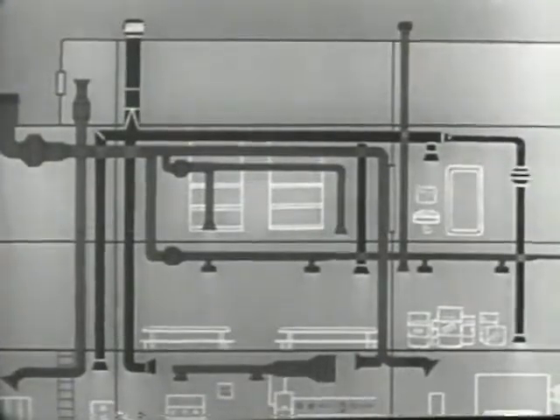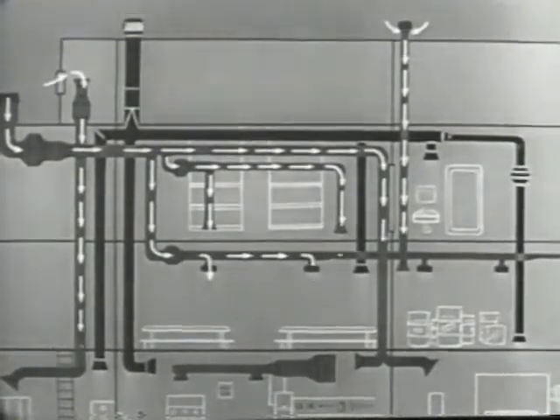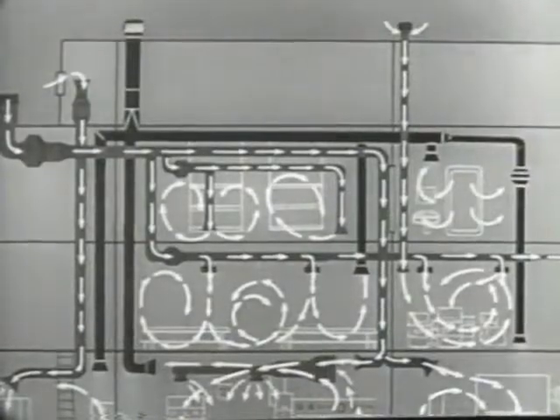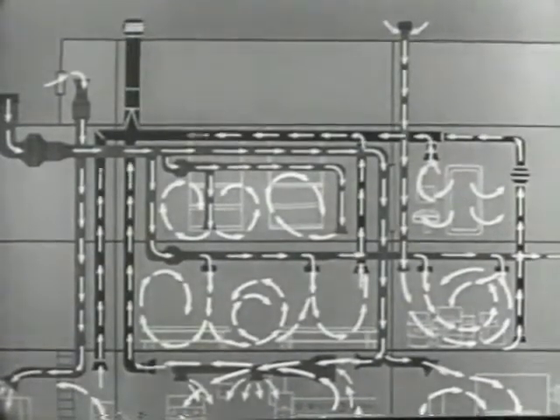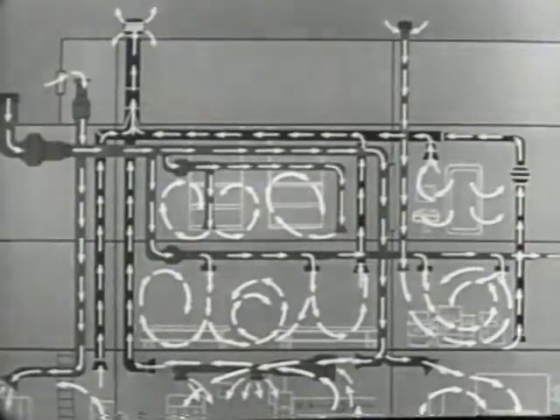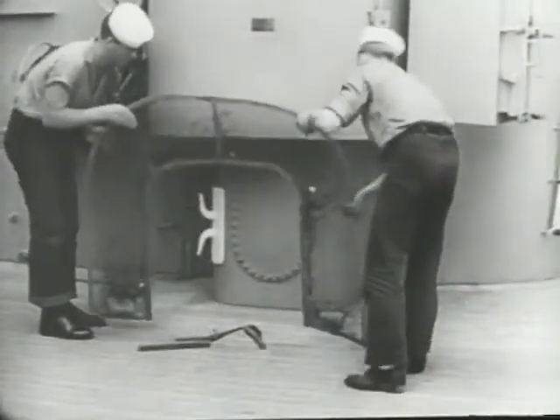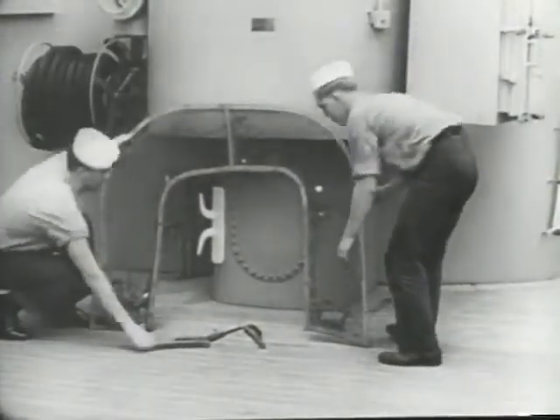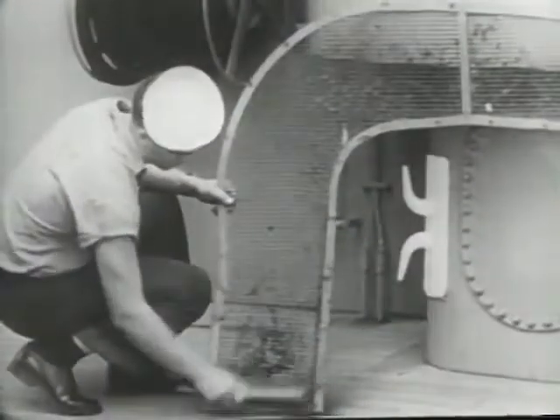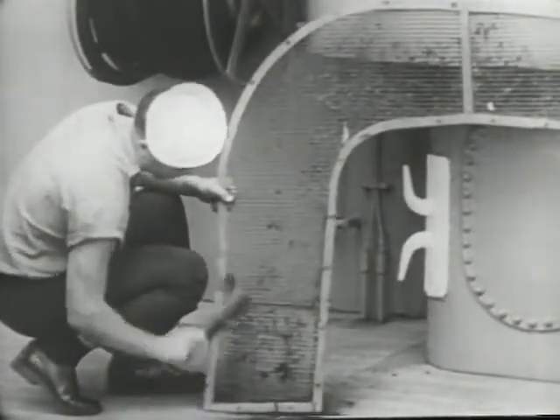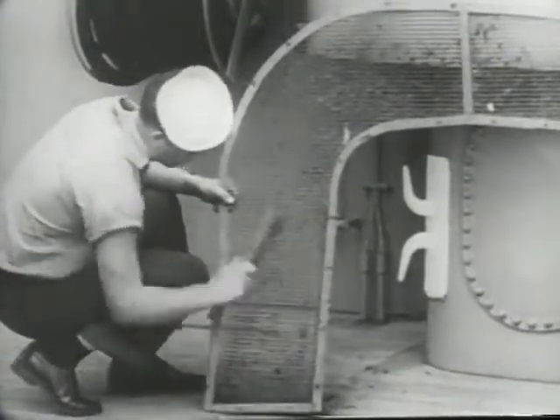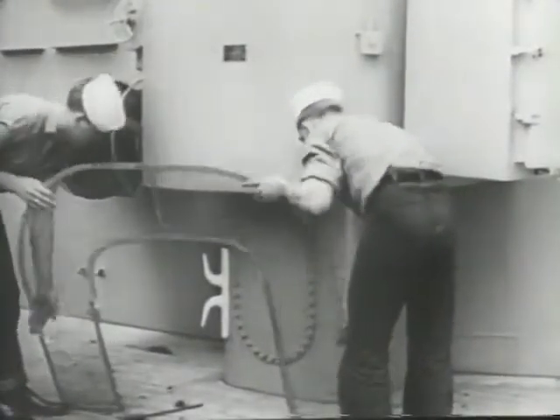A shipboard ventilating, heating, and cooling system is no better than its maintenance. A great quantity of air passes through its elements and accumulates dirt. This cuts down airflow and impedes heat transfer. For example, a 50% reduction in air quantity due to a dirt-matted screen will result in a space temperature as much as 10 degrees higher than intended. Furthermore, dirt obstructions change the flow characteristics of fans and contribute to added noise.